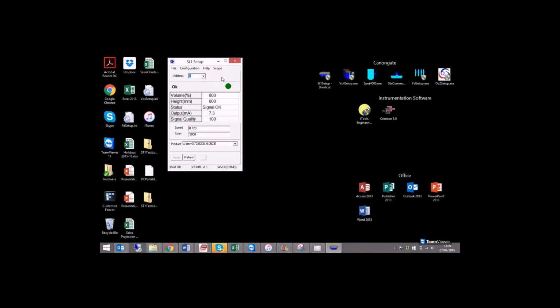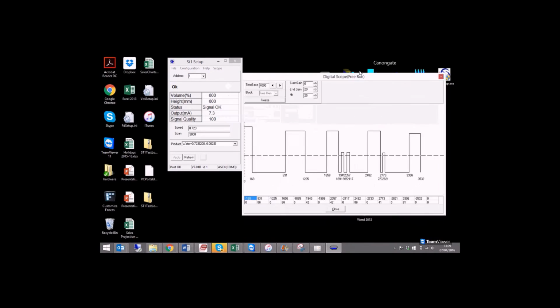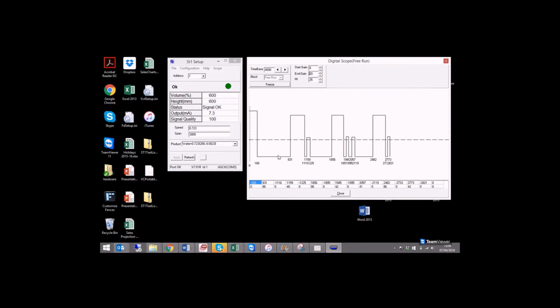In my opinion, the most useful feature of the software is the digital scope. If you click on this button, scope, it will bring up a representation. The two axes here: this is time, and this is echoes that are being sensed. On this particular setting, we haven't got amazing signals, but we've certainly got enough to get by. So this represents an echo hitting the face of the sensor. This is what we call the ring. This is the pulse of electricity which creates the ultrasonic signal.